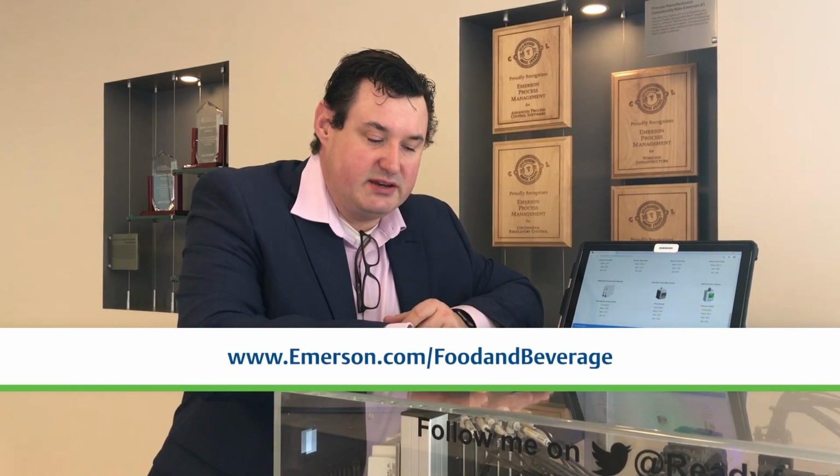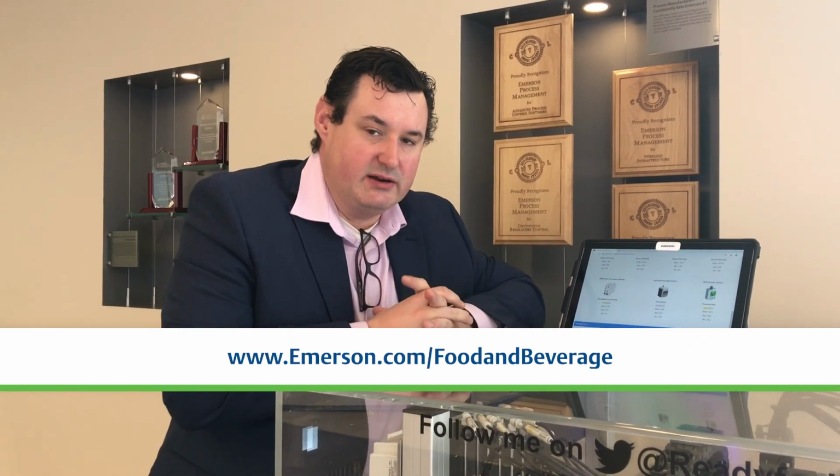By knowing this information, we can start to trend this data, understand if there are any leakages within the system, and understand if there are any problems with the cylinders, whether they need adjusting or to be repaired prior to complete failure. The other thing we can do within the edge device is send notifications, whether that be an email or text message, to get maintenance of the devices prior to complete failure. And that obviously increases the uptime of the equipment and lowers the total cost of ownership.